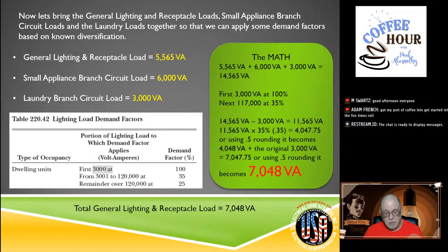Guess what? You're done your first overall step in your calculation where you have added the demand factors for the general lighting and general use, right? Now that's huge, isn't it? What did we go from? We went from, what was it? 14,000 and we dropped over half of that off. We're down at 7,000, okay? All right, so the demand factors are huge. Okay, so we drop that down to 7. So write that down. Let's keep going.